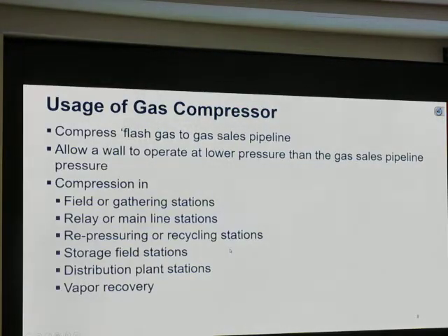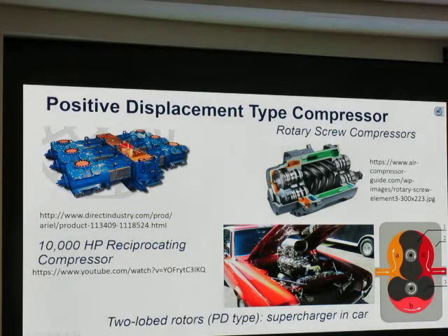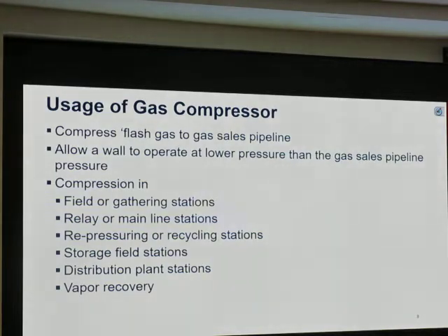The way that screw compressor works, we can use that in a vapor recovery unit. In between there's a liquid or oil to seal it. Gas moves along this screw groove, and then the area gets less and less and less. That's why the pressure goes up. I think we have a video at the end. All right.